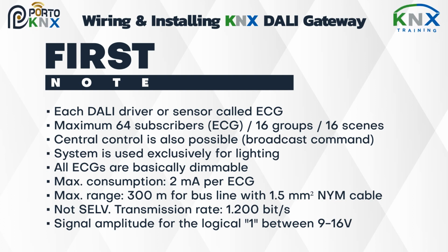Central control is also possible, broadcast command. System is used exclusively for lighting. All ECGs are basically dimmable. Max consumption, 2 mA per ECG.